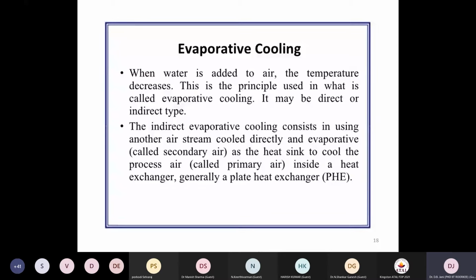Suppose you provide a temperature of 35 at the end of the evaporator, and the humidity is very much below saturation. You will get a temperature difference of around 8 to 10 degrees centigrade from evaporative cooling. In the case of a hot summer, it will give a lot of thermal comfort for the occupants in an indoor environment. But there is one limitation of this evaporative cooling.